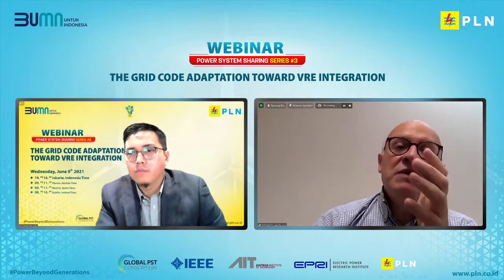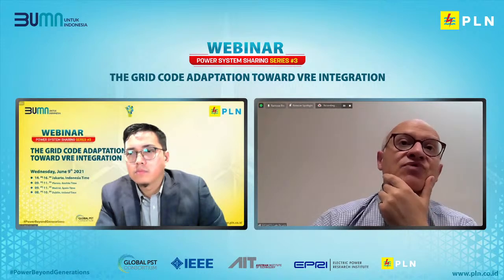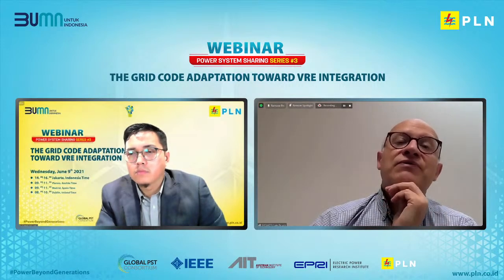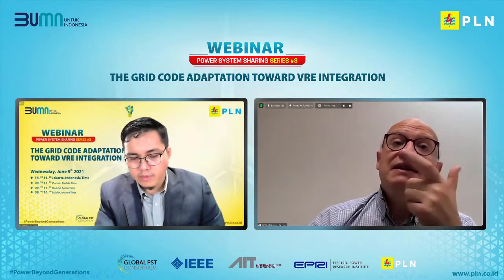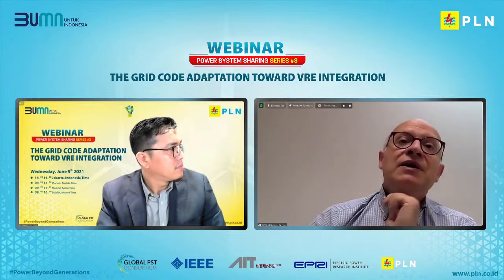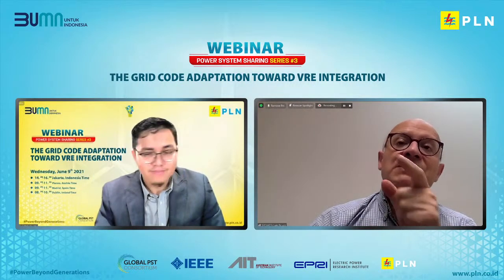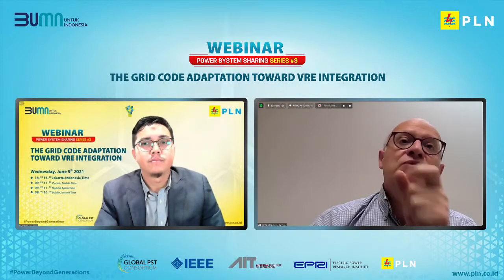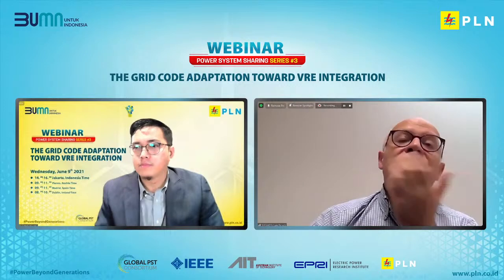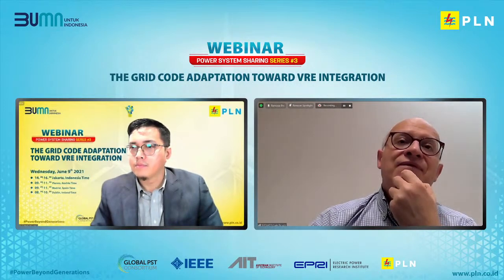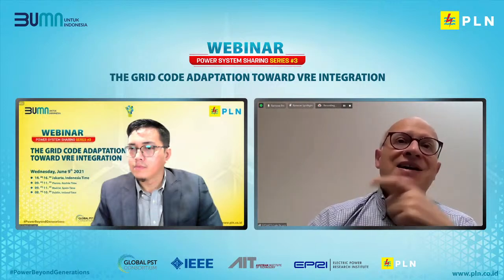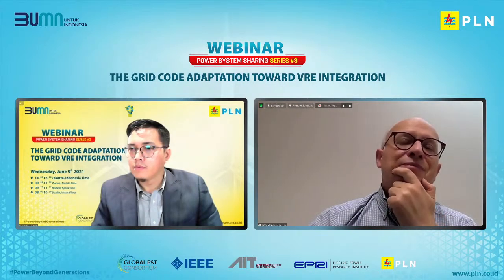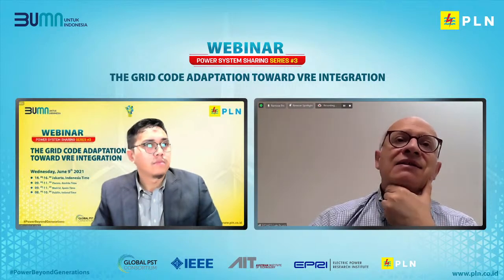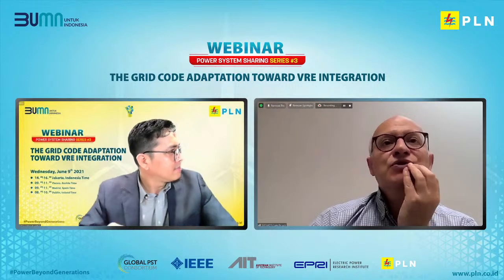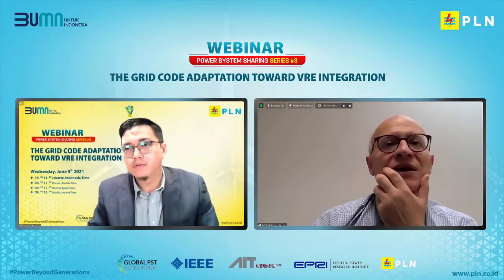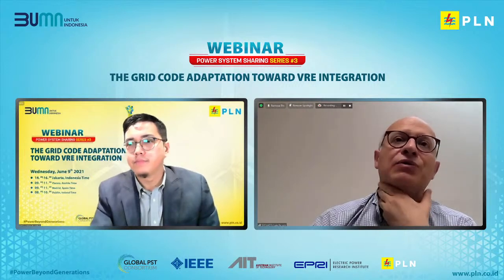What I would say is that inverters must not trip with a rate of change of frequency; it is a ride-through capability based on rate of change of frequency. It means that they should avoid using rate of change of frequency as an approach to detect islanding conditions. There are other approaches, like active methods, which inject a current and then see the response of the system. So it is very important, and I think that the lessons learned from the disturbance in the UK in July 2019 are really illustrative and should be taken into consideration.